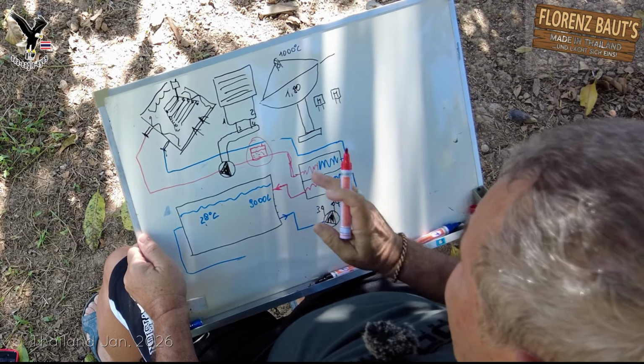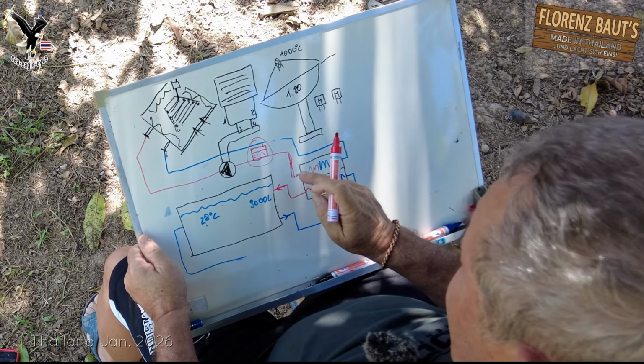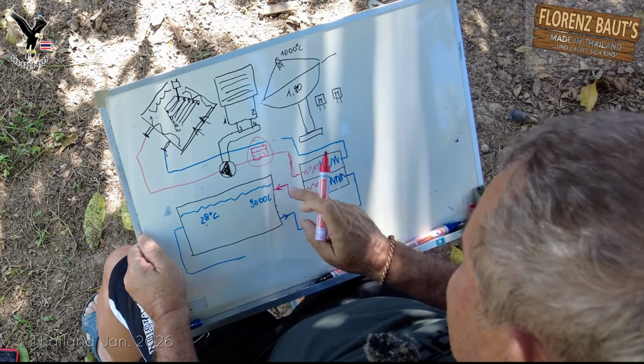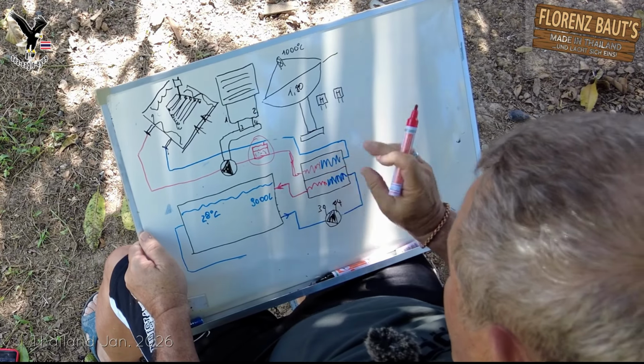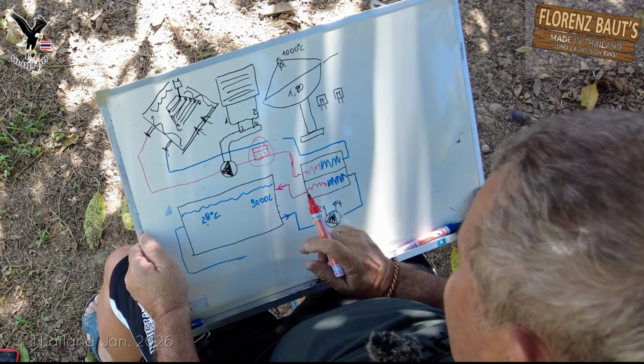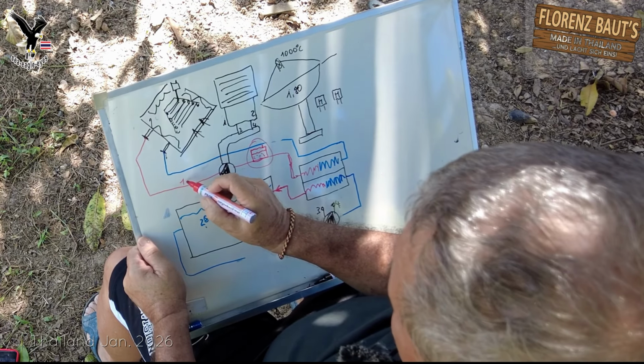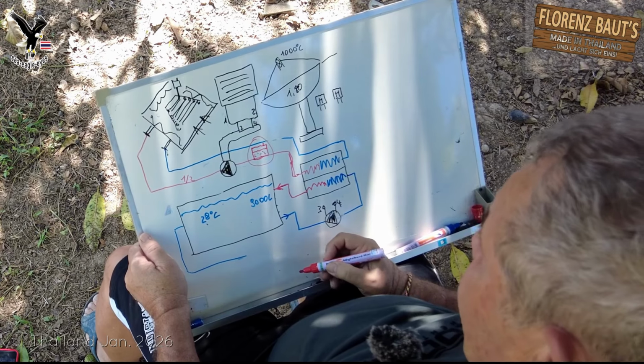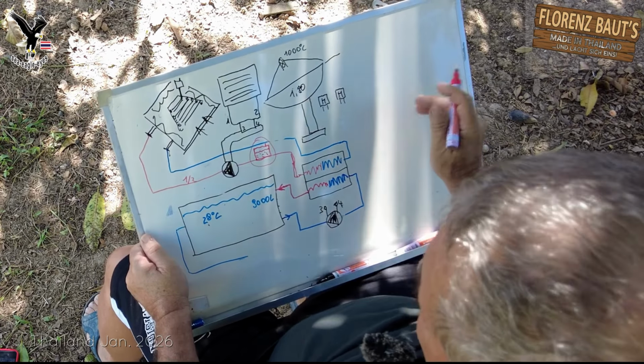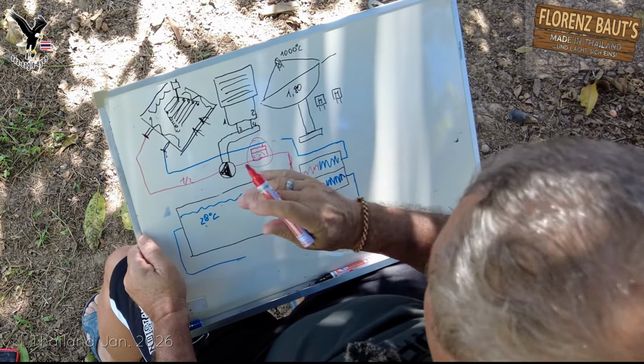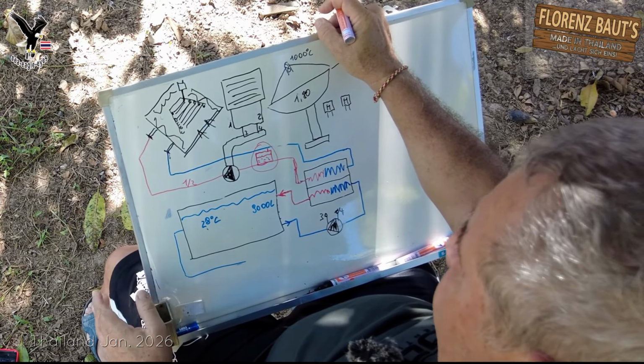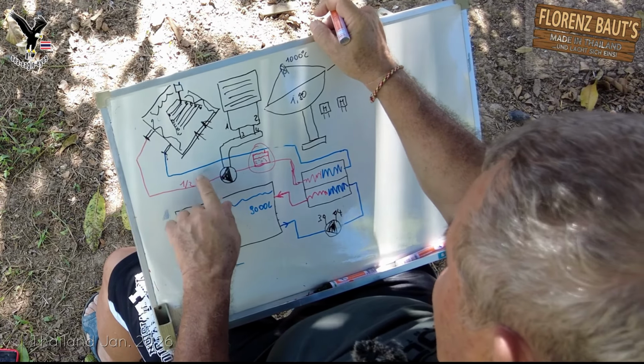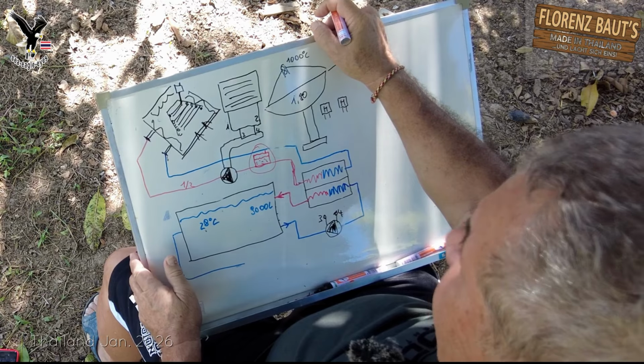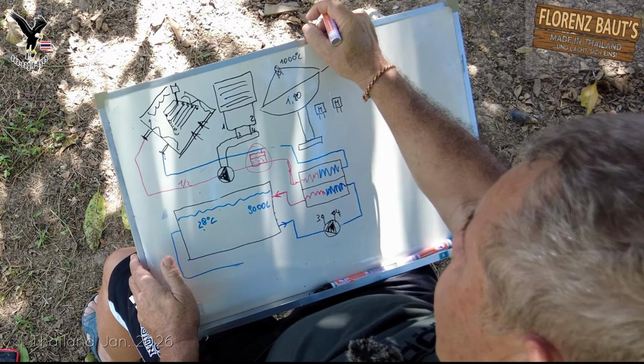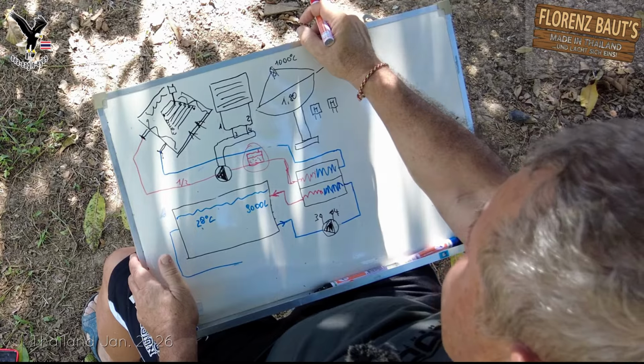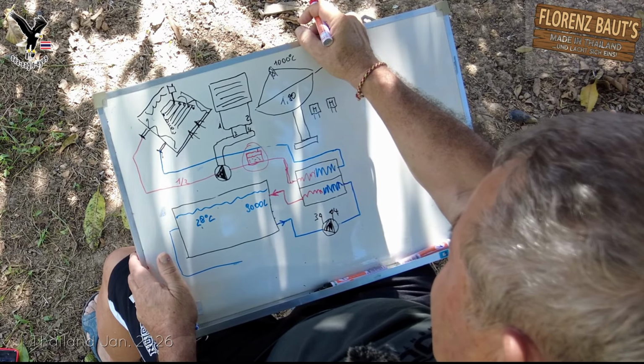So since in my case we are almost 10 meters or even more away from the heat exchanger, I'd like to have the heat exchanger here by the jacuzzi. We need a 1/2 inch line here that is double insulated. It's best to use this here because you have curves. When laying it from a roll, soft annealed copper pipe is best to use here. And that is then insulated with insulation material that can withstand at least 100, 110 degrees.